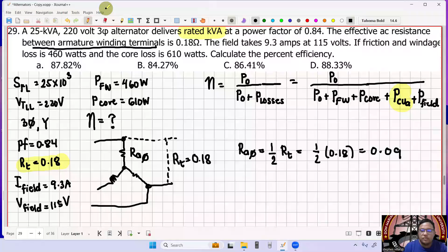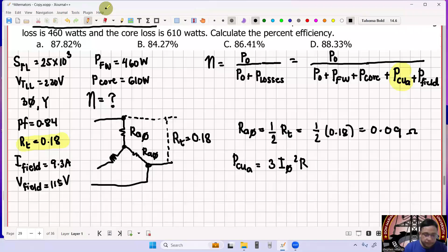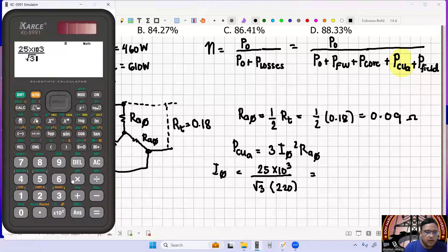From here we can get our total armature copper loss. This is equal to 3 times our I per phase squared multiplied by RA per phase. But we don't have I per phase yet, so how do we get that? From our rated load. This is now equal to 25 kVA over square root of 3 multiplied by 220, which is 25 times 10 raised to 3 over square root of 3 times 220. This is equal to 65.608 amperes. So let's put this here: 3 times 65.608 multiplied by 0.09.